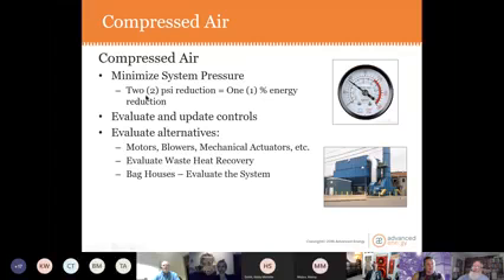There's a rule of thumb that if you can reduce your air pressure by 2 pounds per square inch, you can save 1% of the compressor energy. So if you're running at 120 and only need 100 and can reduce your air pressure to 100 psi, that's 20 psi. That's 10% of the cost of the energy to run those compressors. Controls, updating how the compressors are started and stopped, looking at alternatives to compressed air. Use a 20 psi blower, use some kind of mechanical actuator.